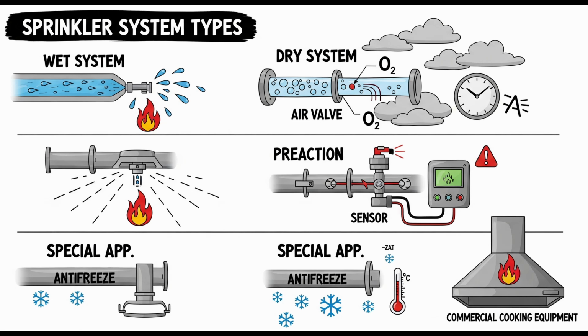What's that about? This is mainly for dry pipe valves that use a pressure differential to hold back water. They're called differential dry valves, or where the valve design allows it to potentially reseat after tripping without fully draining all the water above it. Okay. Why is high water a problem there? If water accumulates above the valve clapper, it reduces the effective pressure differential holding the clapper closed. This makes the valve more prone to false tripping from minor system air pressure drops. Plus, that water could freeze and damage the valve in cold weather. So it compromises the seal or risks freeze damage.